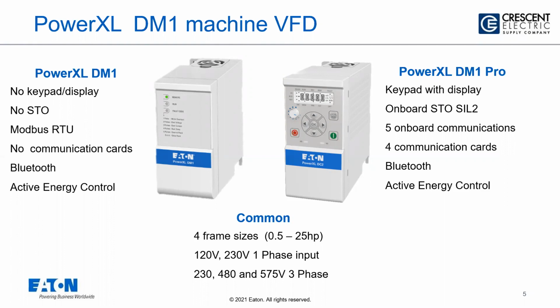The DM1 does have some built-in communications. The DM1 Pro then will allow you to stick option cards into it for additional communications. The DM1 does not carry a safe torque off. If you want that, we have to move up to the DM1 Pro, and that's going to be your SIL 2 category. Both of them do have Bluetooth though, which is really nice. So you can connect up with a laptop, for example, and you can monitor it, access web pages, as well as program it. And we have a common programming environment called InControl, which is going to allow you to not only program and monitor and configure the DM1 or the DM1 Pro, but also will allow you to do the exact same thing with our flagship DG1, which is our industrial drive.